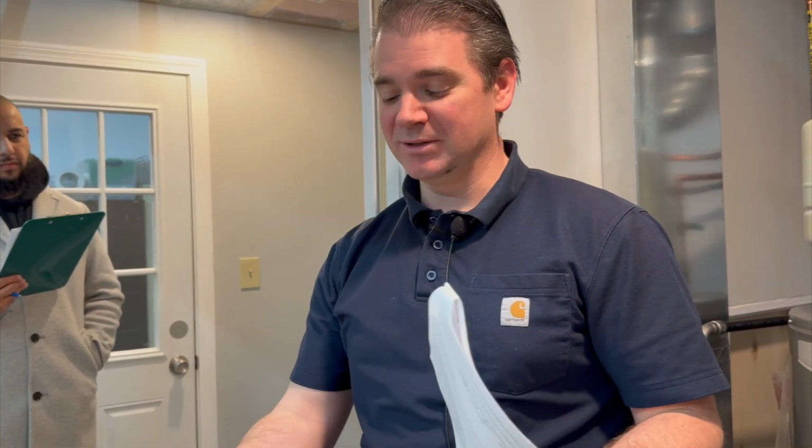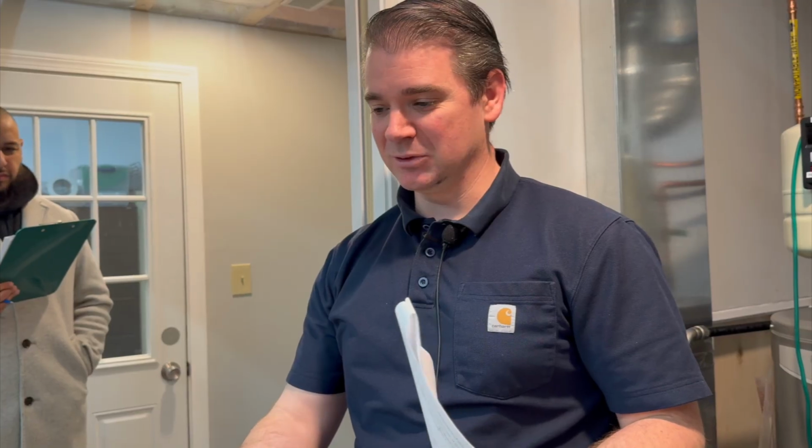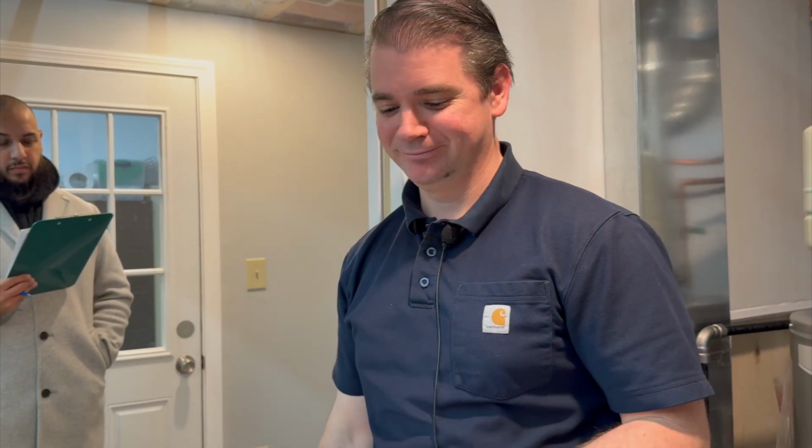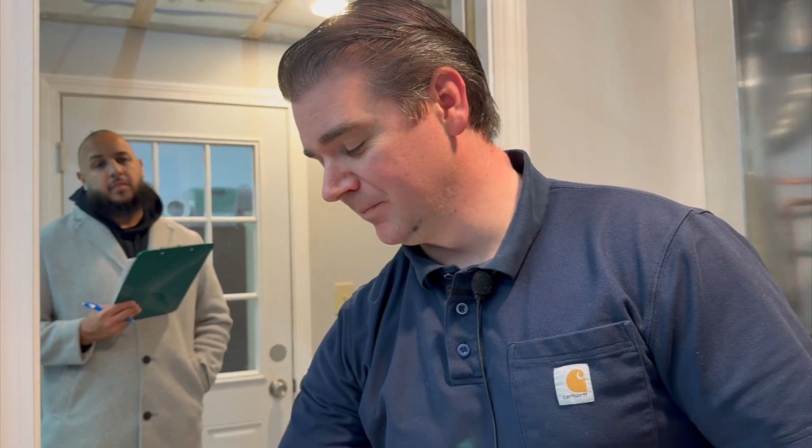Explain the difference in blower door equipment setup for depressurization versus pressurization. Well, for the manometer, the hoses are basically the same, but you just want to follow their quick guide for setting it up. For the fan, that's the primary thing. Some fans have a little switch that'll change the direction of the airflow, or if it doesn't have that, you just have to turn the fan around.